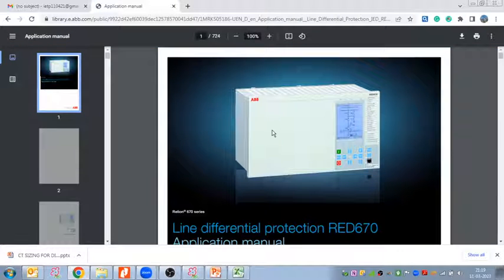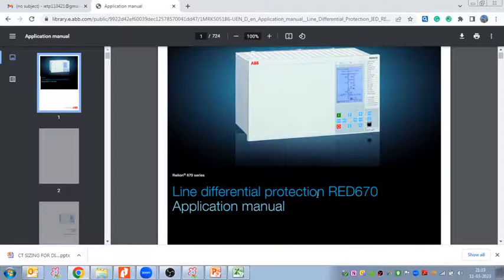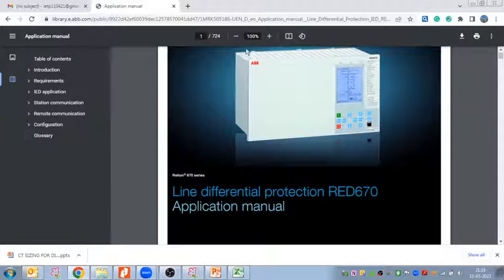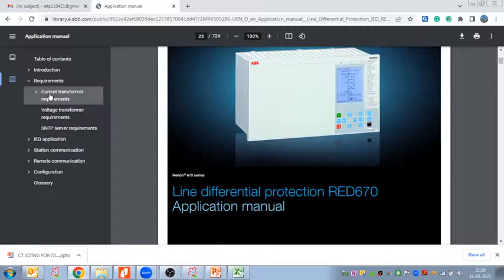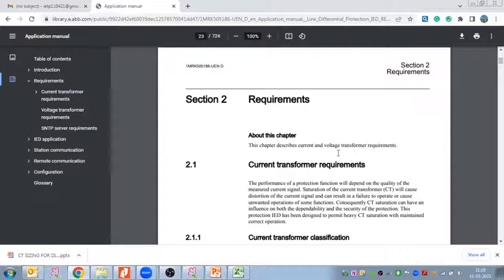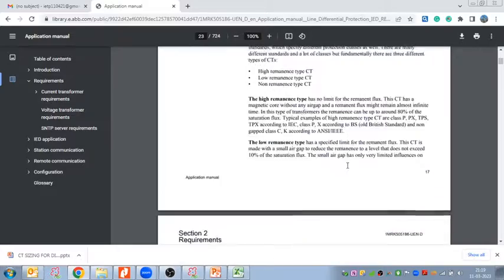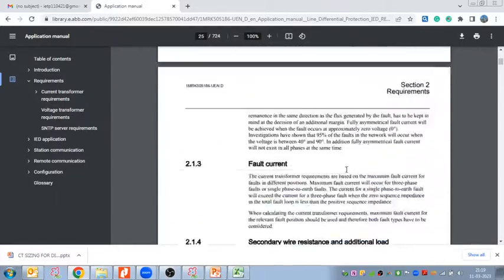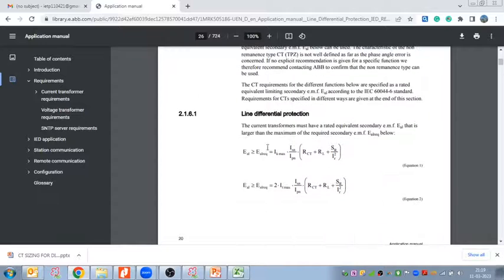So now this is the RED 670 line differential protection, because we have decided what kind of protection is required, right? So go here, go to your CT. For CT requirement, go to the requirements and click on current transformer. You will directly reach the page: Section 2, requirements, current transformer requirement. So here, if you are using differential protection for your transmission line, then these two equations you need to solve.